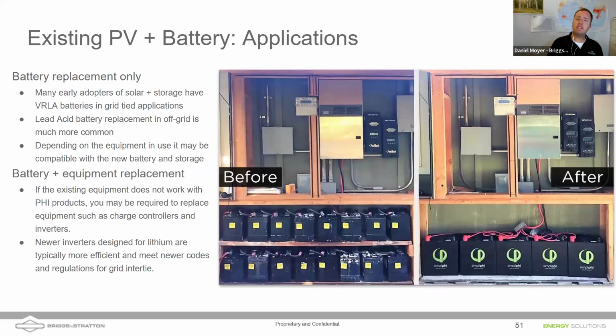100% depth of discharge is warranted, but I'd still recommend 80%, so when you hit that low battery cutout voltage you still have reserve capacity left to run the inverter, since inverters have that standby draw I mentioned. But for a system that isn't cycling a lot, sure, go ahead and get it to 100% depth of discharge - you can do that, and we still warranty for it. Mike, anything to add?